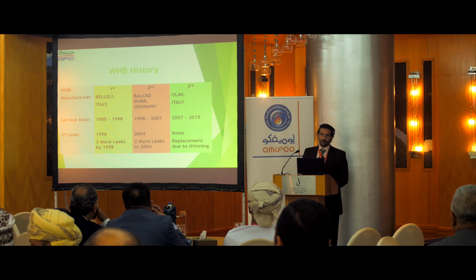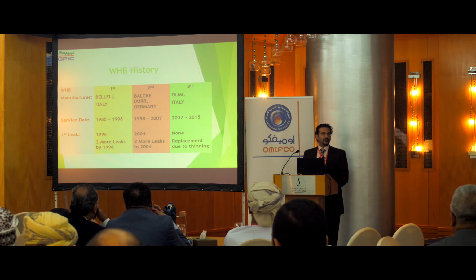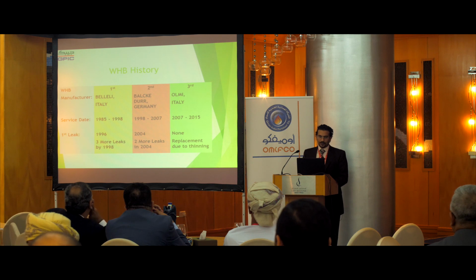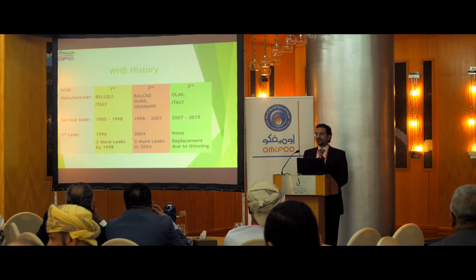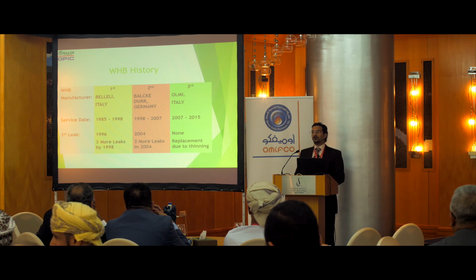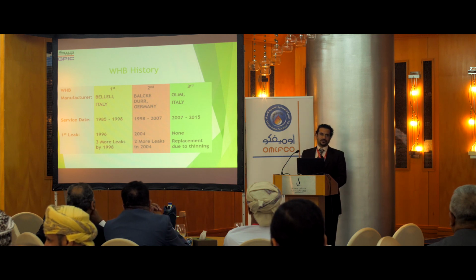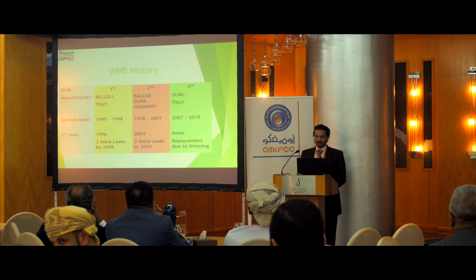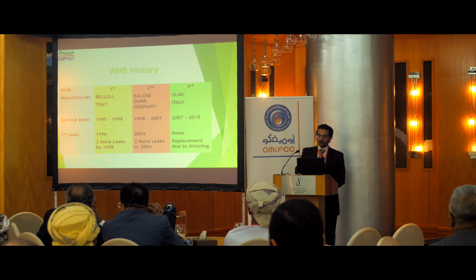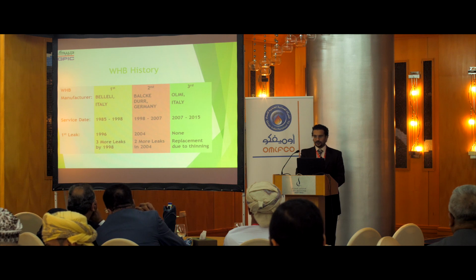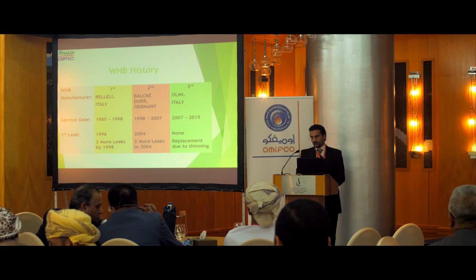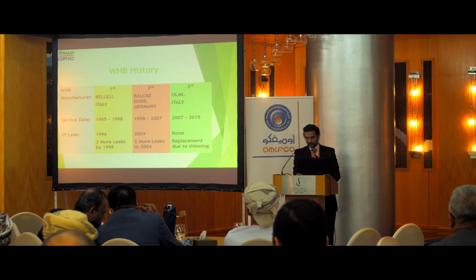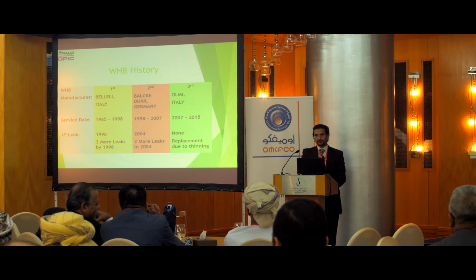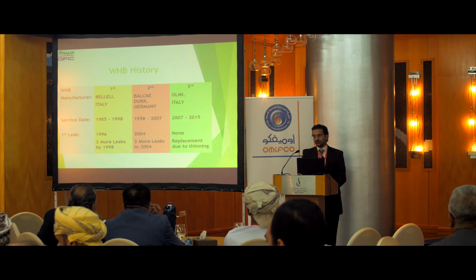This is our waste heat boiler history. Our first waste heat boiler was manufactured by Bellelli, Italy. Its service date was from 1985 to 1998, where our first leak was in 96, and then we got 3 more leaks by 98. The second waste heat boiler was Balke-Dörr from Germany, 1998 to 2007. First leak was in 2004, then 2 more leaks in 2004. Our third waste heat boiler was manufactured by Olmi, Italy, from 2007 to 2015. We did not have any leaks or problems with this waste heat boiler.